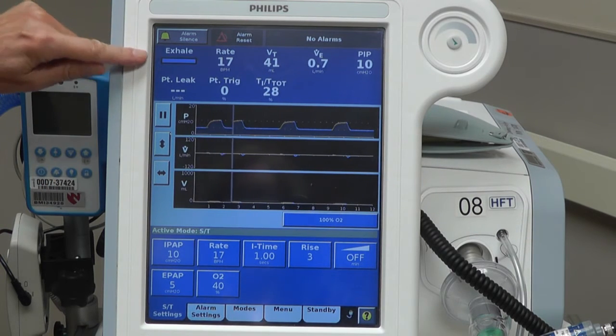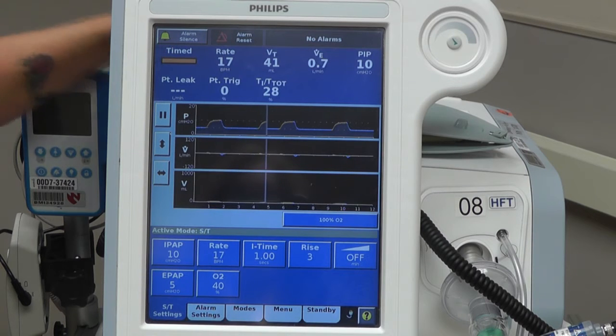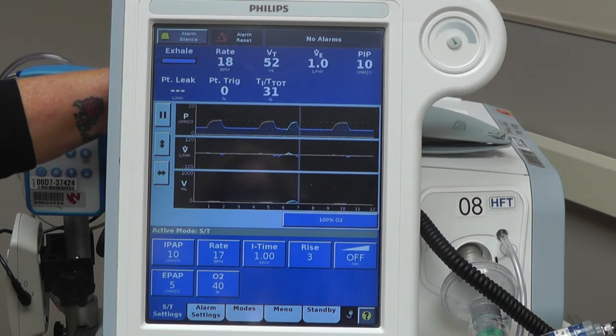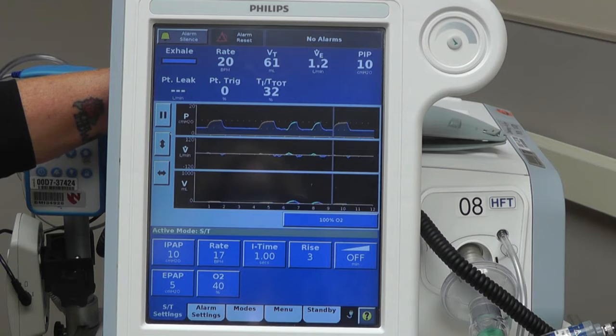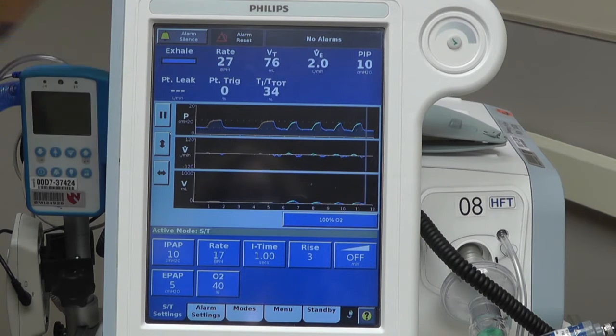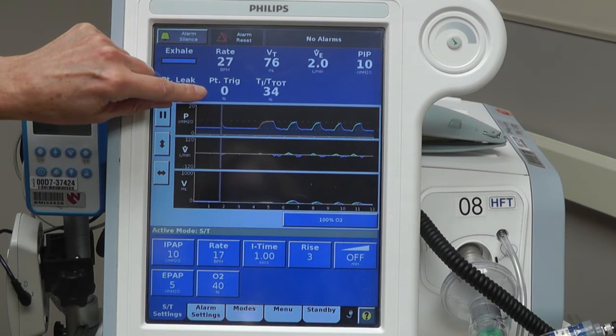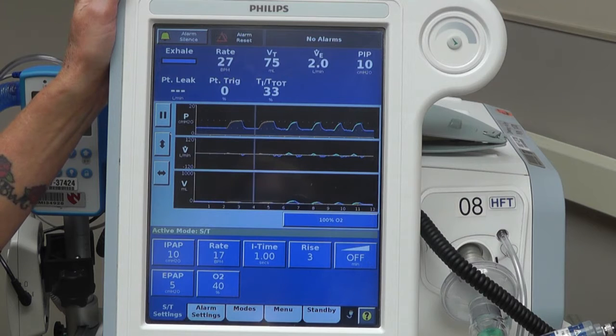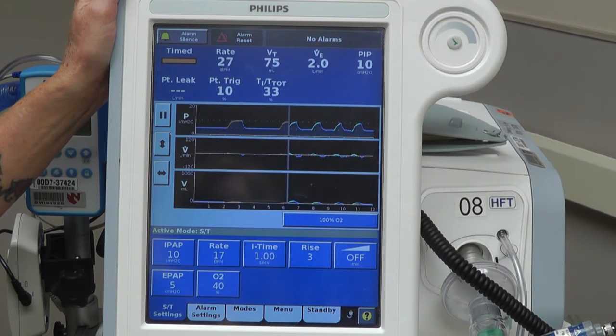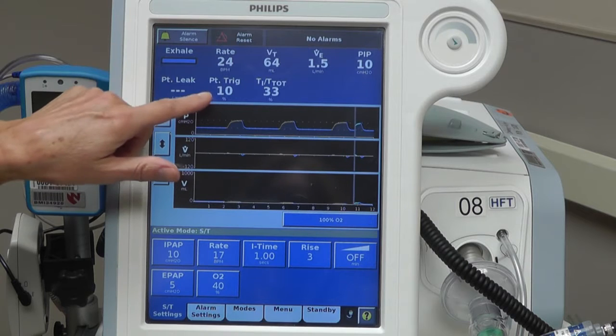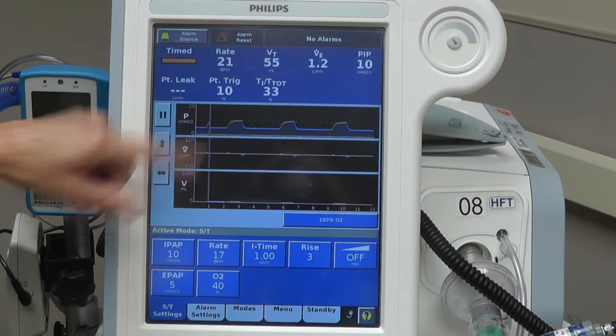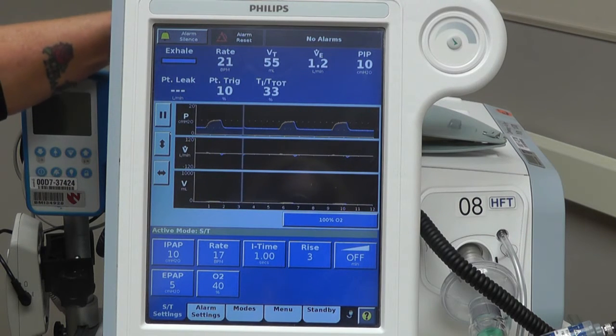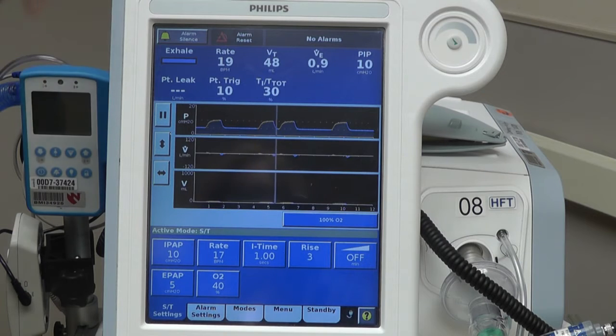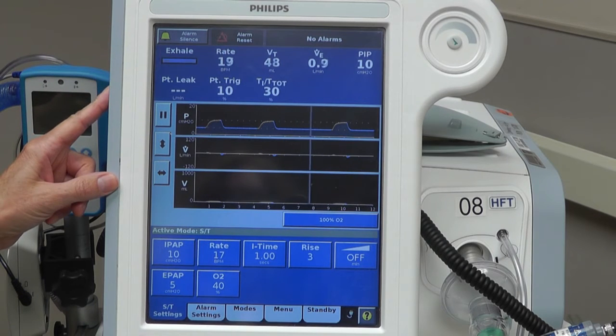So you'll see here that this is a timed breath. You should see it showing up as a spontaneous breath. And then right here, the patient trigger. The patient trigger should be near 100% all the time. So 90-ish% is what you should see here in a patient trigger. If you see anything low like this, then that's concerning that your patient's not breathing on their own. And you're going to want to call your respiratory therapist to troubleshoot this.